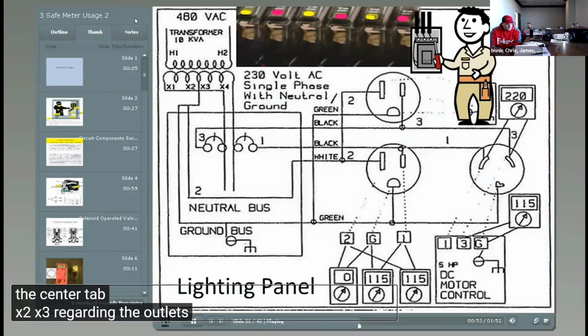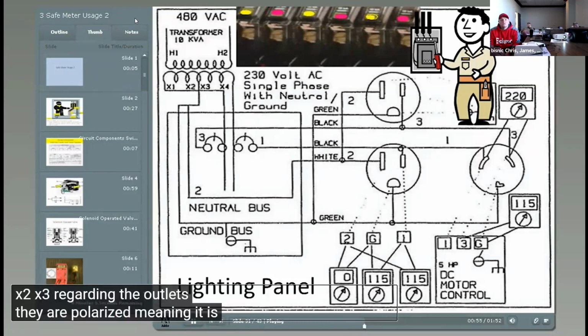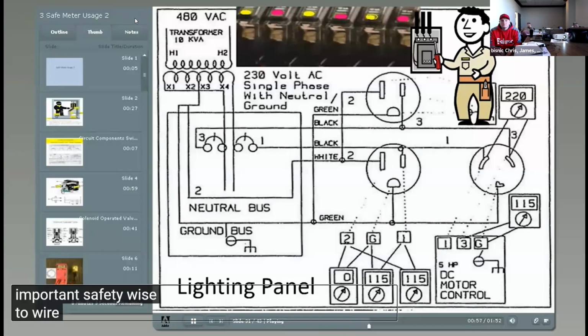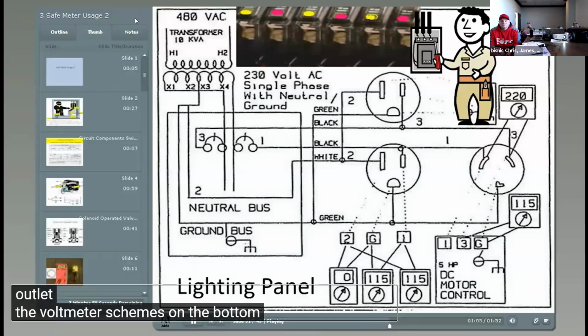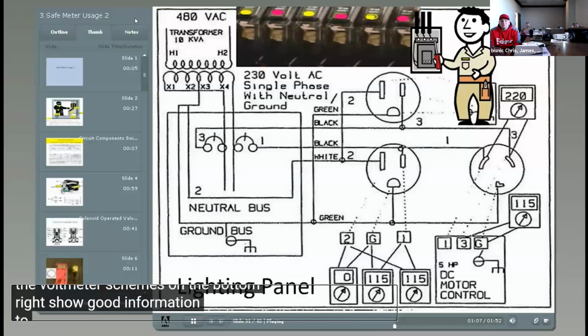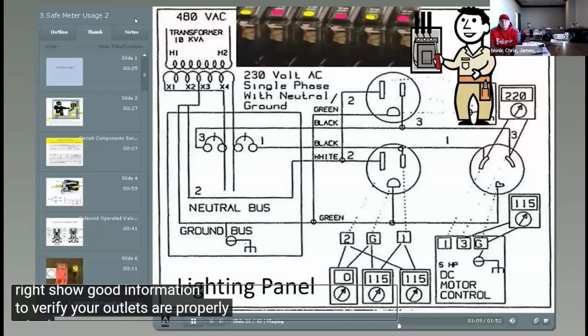Regarding the outlets, they are polarized, meaning it is important safety-wise to wire the neutral wire, the ground wire, and the hot wire to their appropriate terminals on the outlet. The voltmeter schemes on the bottom right show good information to verify your outlets are properly wired.